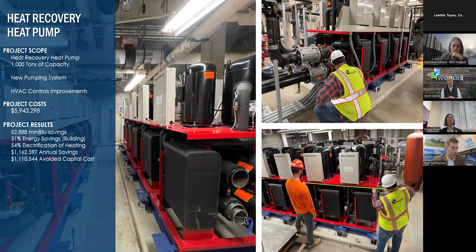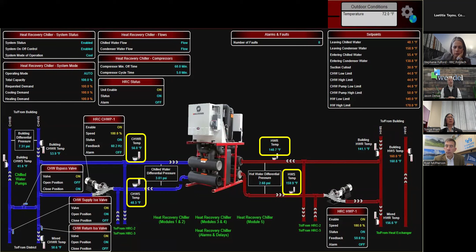These heat pumps provide chilled water that your facility department would love, and hot water at the exact same time that they'll also love. All it's doing is transferring energy from the chilled water side. Remember, heat pumps transfer energy, they don't generate it. So it absorbs energy from the chilled water, creating more chilled water, and puts that energy over to the hot water side, rejecting heat and offsetting the use of steam boilers. In fact, this is the actual steam meter that served this area of campus.